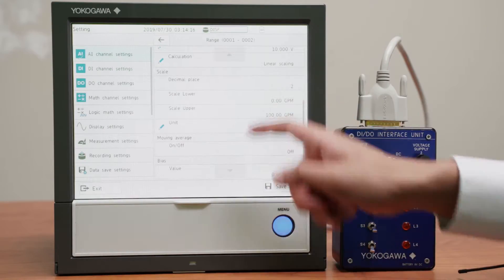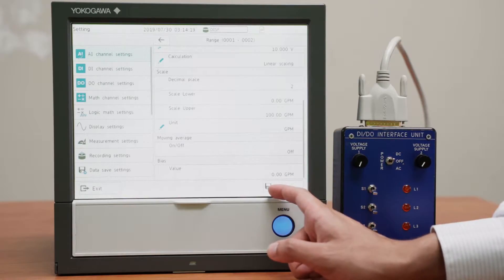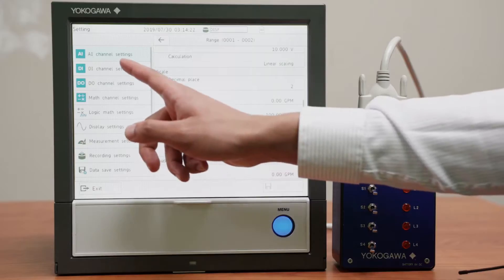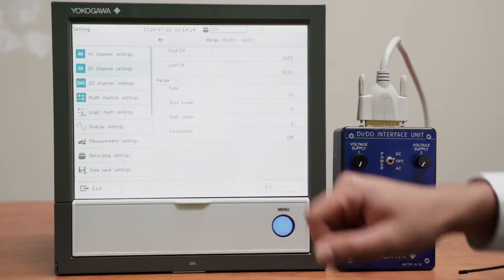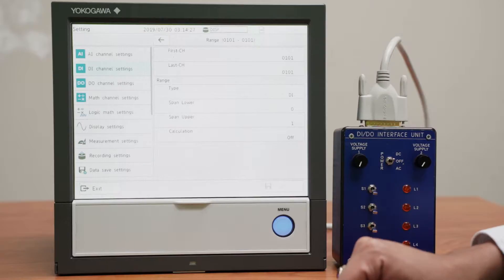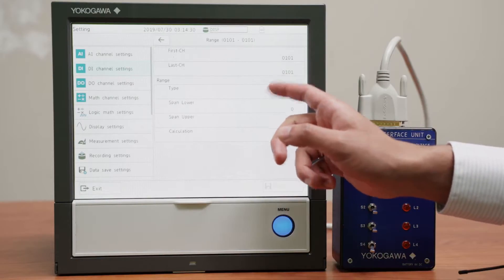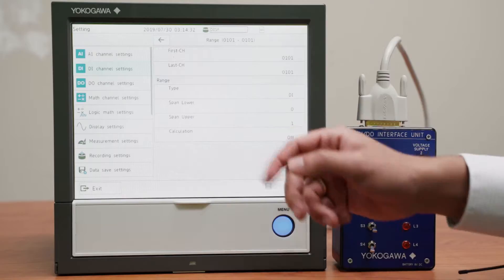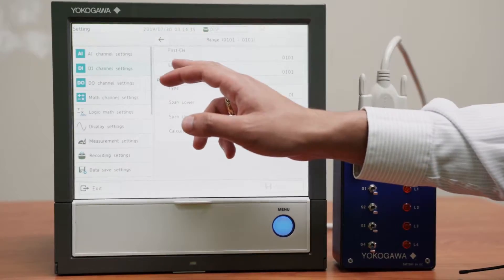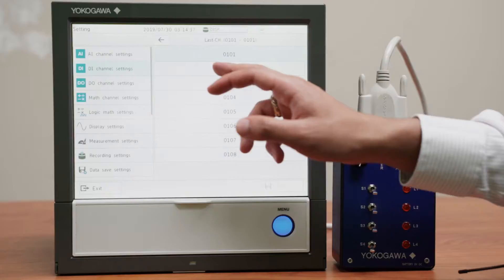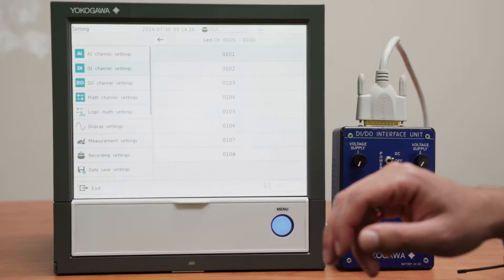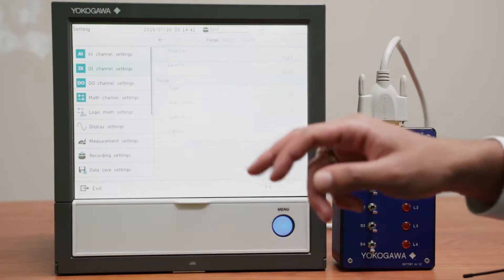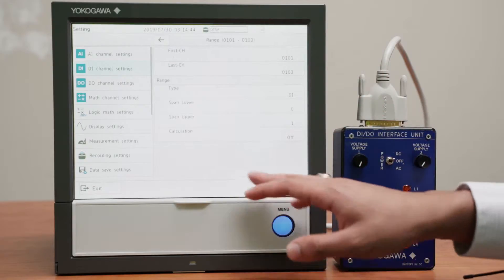I will need no moving average and no bias. Next I'll make sure that the DI channel settings are set correctly. They should be set to default. Type is DI, span lower 0, span upper 1, no calculation. Same for all of the channels from 1 to 3 and it is correct.